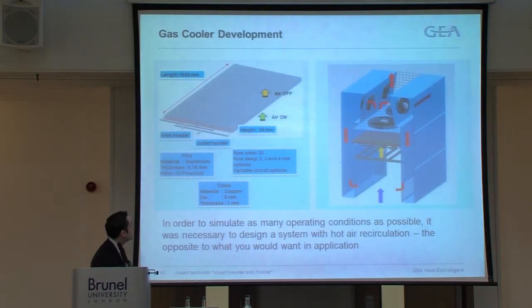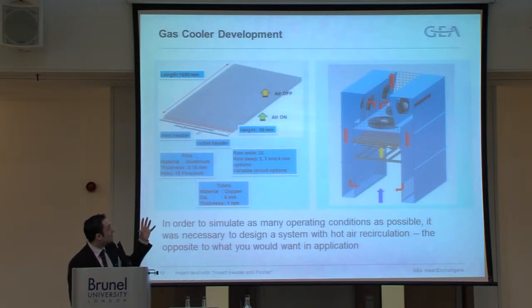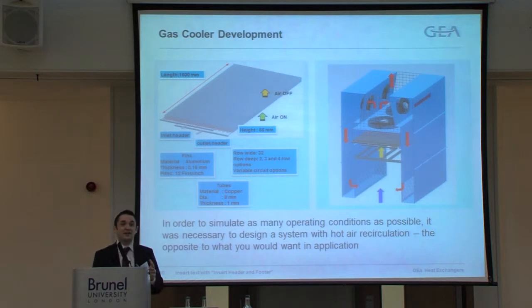So this follows on to the gas cooler. It doesn't look like you would expect to see on the top of a supermarket. And that's because we wanted to be able to increase these temperatures up as high as 40 degrees C air inlet temperature, so for the peaks of summer in some parts of Europe, not in the UK, unfortunately. So we were doing the opposite of what you might expect to see, and that's recycling the hot air from the air off face of the gas cooler. So we calibrated this at the GEA Searle wind tunnels to ensure that those extra fans weren't going to have any effect on the airflow over the coil. We also did have some heater elements there so that in the summer months we could take it even higher as required.